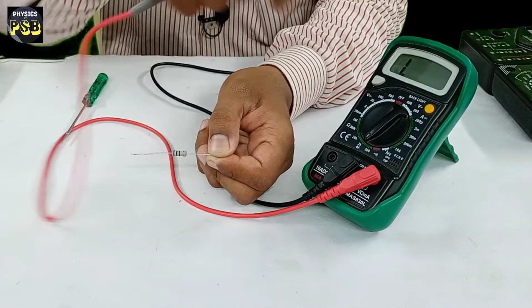Now I'll set the lowest range for accuracy. See, now the value read is 98.7 ohm. The actual resistance of this resistor is 100 ohm, but it has got some tolerance, so the actual resistance measured is less than 100 ohm, at 98.7 ohm.